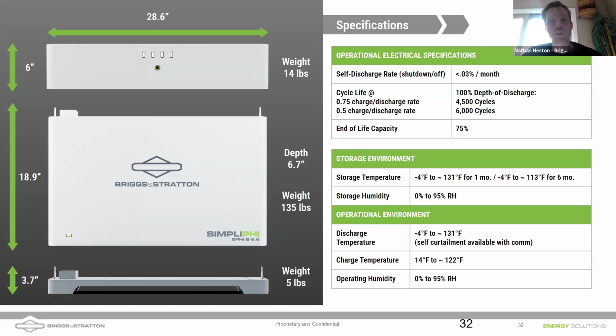And then we can discharge the battery all the way down to -4 Fahrenheit, right? So if it's that cold day, you need the power and the batteries are already charged, you're good down to -4 Fahrenheit. Below -4 Fahrenheit, the battery BMS will protect itself and prevent the battery from discharging. So if you're in an extremely cold situation, there is the potential that your battery won't be able to discharge. For that reason, in sites where you're getting consistently low temperatures, we recommend installing indoors, potentially in a utility shed, or inside a garage, especially on an interior facing wall.